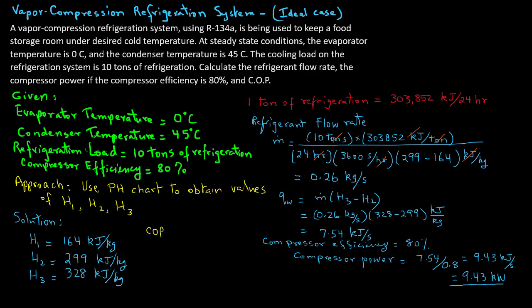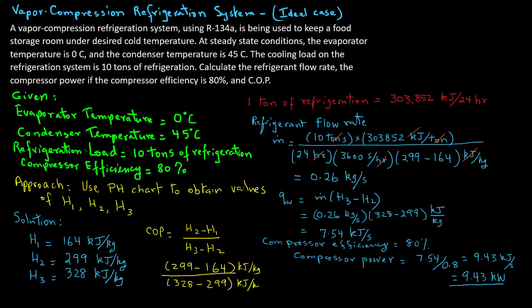The coefficient of performance (COP) is calculated as (H2 minus H1) divided by (H3 minus H2). With values of (299 minus 164) in the numerator and (328 minus 299) in the denominator, the COP equals 4.66. Note that the coefficient of performance for vapor compression systems usually varies between 4 and 6, so our value of 4.66 makes sense.